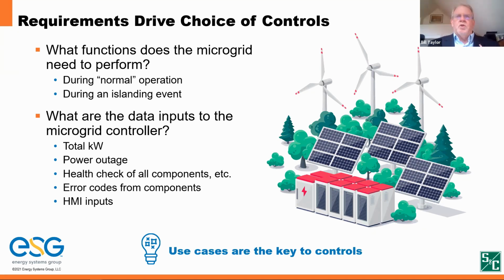What's going to happen there? What functions have to occur? I've recognized the utility's gone. I've closed the circuit breaker. I'm now island mode from the utility. What does that controller have to do? Is it going to do a heartbeat? Is it going to continually check my status of my system, or the microgrid system, the redundancy system, the N+1, everything that I need to make the base run? It's going to continually check to make sure that when that island switch is thrown, everything works.